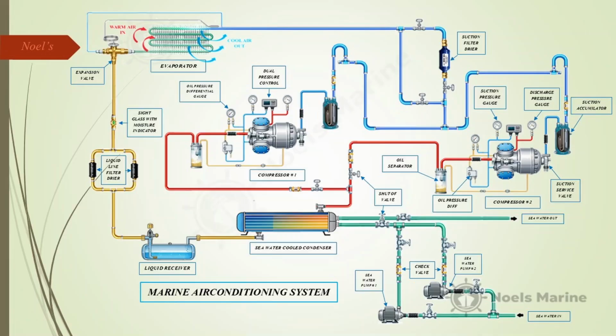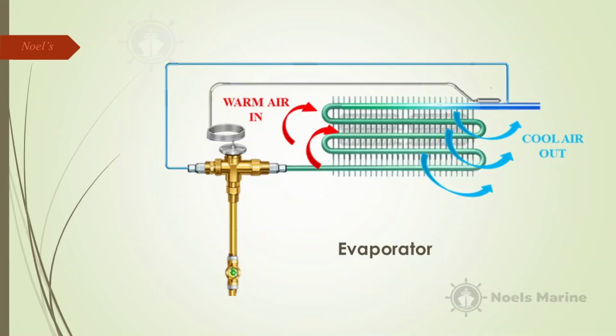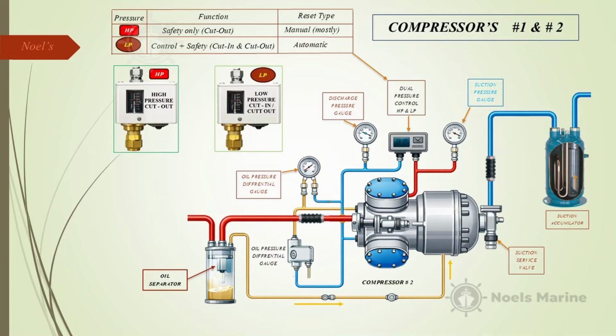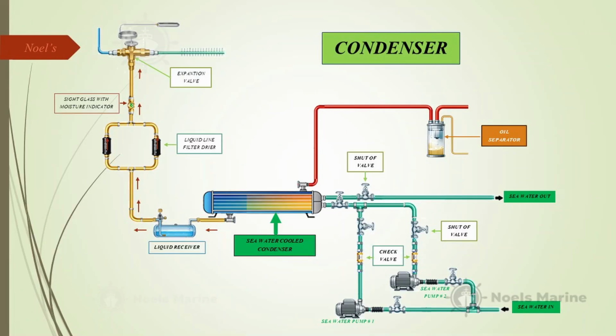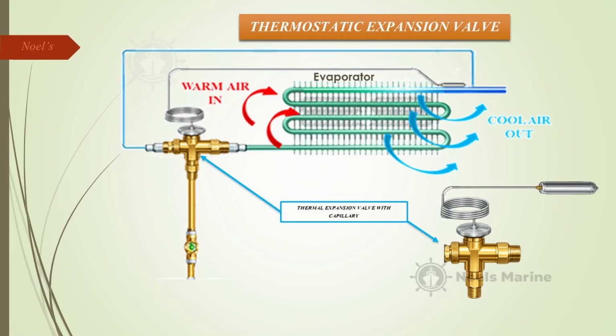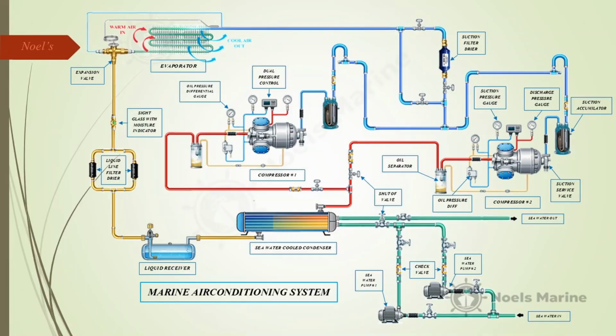Yeah. Okay, let's do a rapid-fire recap for you listening to lock in these states. I'll name the component, you give me the pressure summary. Ready? Let's do it. Leaving the evaporator. Low pressure superheated vapor. Leaving the compressor. High pressure superheated vapor. Leaving the condenser. High pressure subcooled liquid. And leaving the expansion valve. Low pressure flash mixture. Simple, clear, and perfectly balanced. And you have to remember, this loop runs 24 hours a day, 7 days a week, nonstop, just to keep the crew safe and effective.